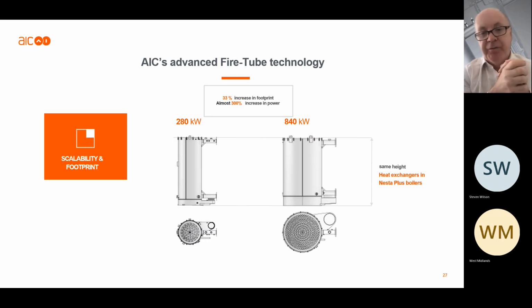Okay, we talk about the footprint. This is given a footprint of the heat exchanger, and the way the heat exchanger is designed, the bigger the output, the more tubes that we put on it. So we put them in a circular fashion. So you can see 280 kilowatt to 840 kilowatt. So you're looking at about a third bigger footprint, but almost 300% increase in power using this type of heat exchanger.